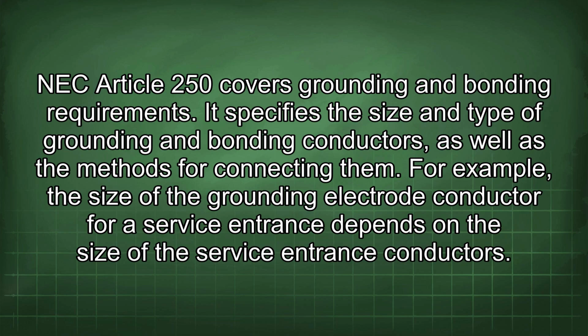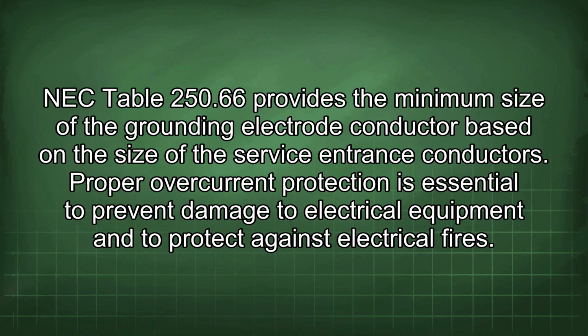It specifies the size and type of grounding and bonding conductors, as well as the methods for connecting them. For example, the size of the grounding electrode conductor for a service entrance depends on the size of the service entrance conductors. NEC Table 250.66 provides the minimum size of the grounding electrode conductor based on the size of the service entrance conductors. Proper overcurrent protection is essential to prevent damage to electrical equipment and to protect against electrical fires.